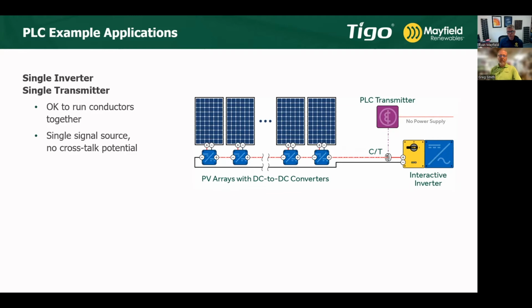So the first step is we lose power, and the power to the power supply goes away. At that same moment, because the power supply goes away, we lose our signal, and the interactive inverter also turns off. This is where the rapid shutdown part comes into play, because without module level power electronics, or without rapid shutdown, those conductors from the PV array all the way to the inverter are still hot, there's still full voltage on them. So what ends up happening is because the signal went away, our module level power electronics turn off.